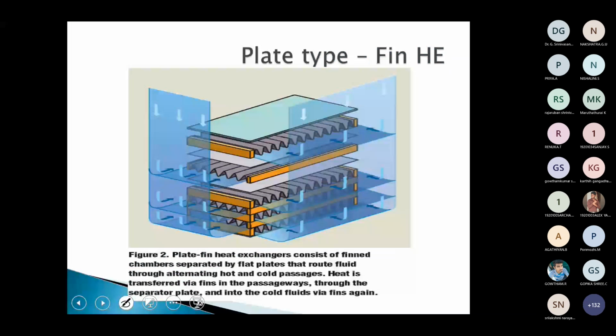This is the plate type fin heat exchanger. When fins are provided, you can see this is not a normal plate. This is a fin type plate. So in order to provide a larger surface area, we use fins as we do in double pipe or in shell and tube heat exchangers. Here also the fins are employed to improve the rate of heat transfer.